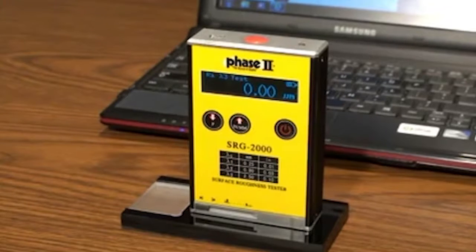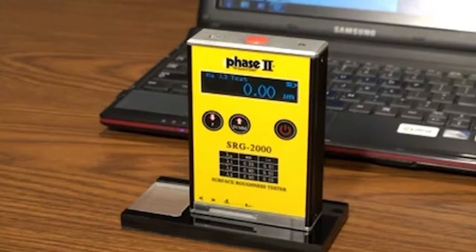The technology used incorporates an instrument in which a diamond stylus is automatically traversed across the specimen and a piezoelectric pickup records all vertical movement. Peaks and valleys are recorded and converted into a known value of a given parameter.